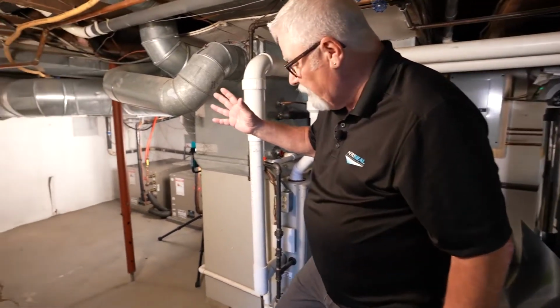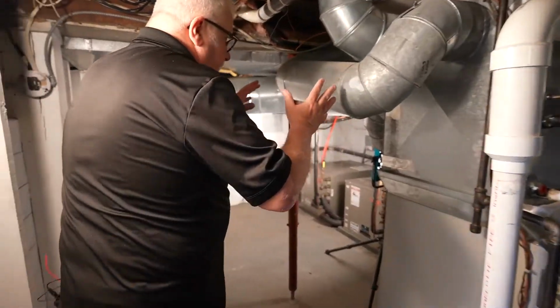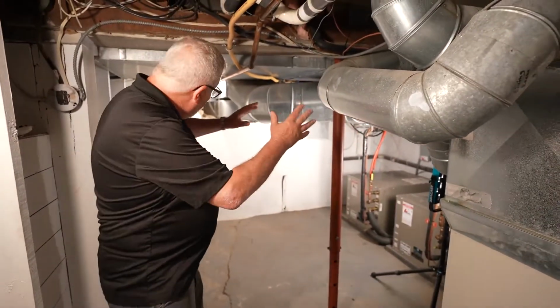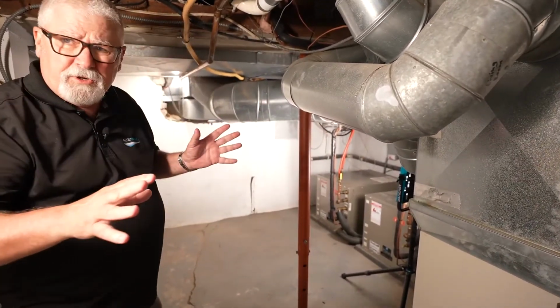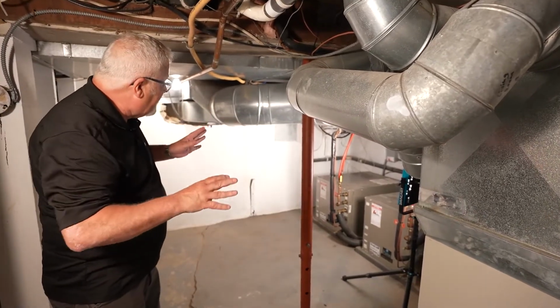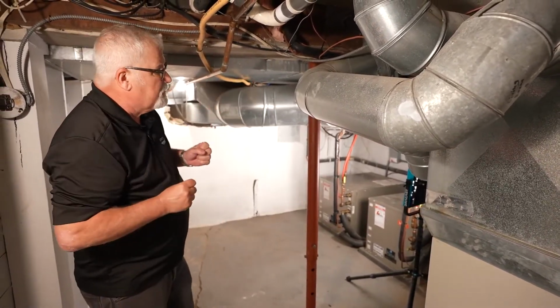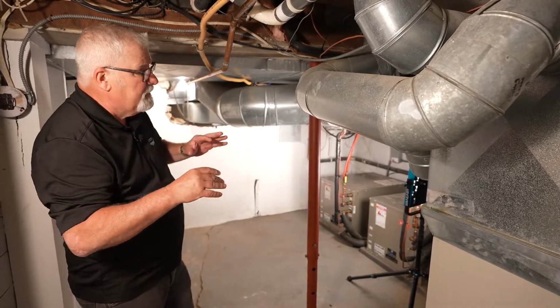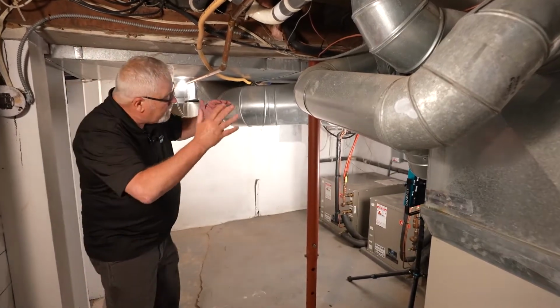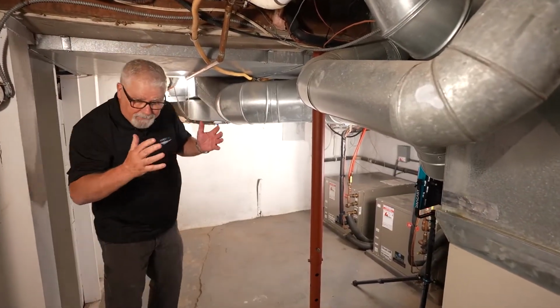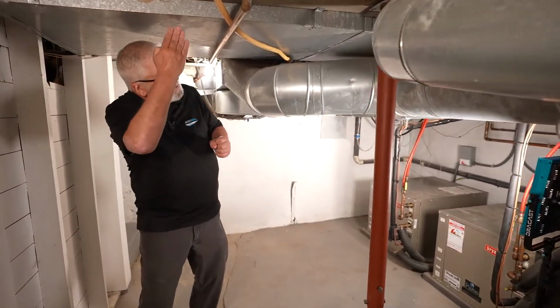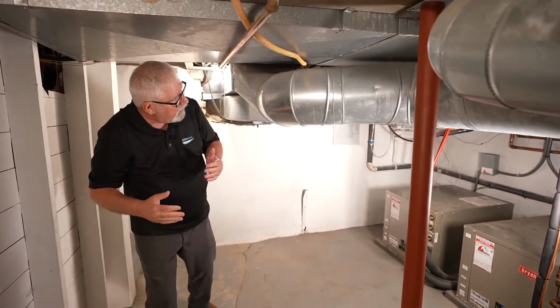As we go through the basement, I've got sheet metal ductwork on my supply side that meanders down into a crawl. I'm not too concerned about that because we can seal it with Aeroseal. There's a lot of sheet metal ductwork down here too on the return side. But unfortunately some of this return has been put into what we call a panned-off joist bay. Right here you can see it, we're panning off a section of it.